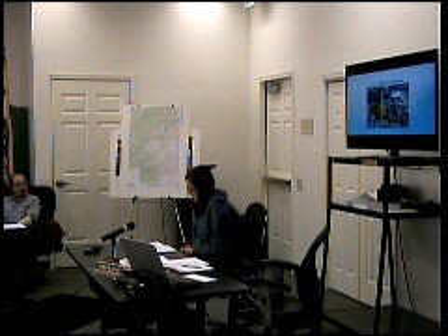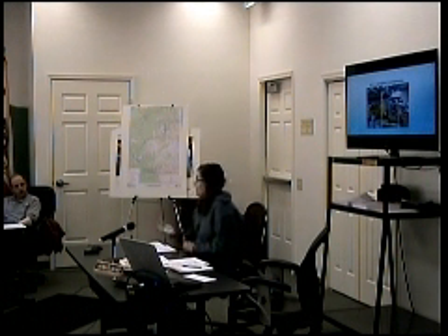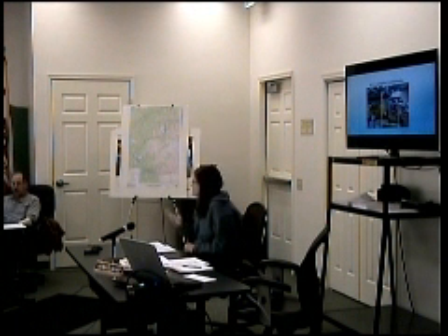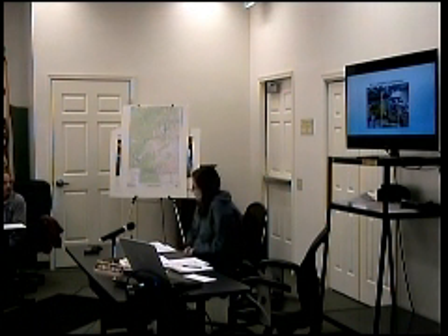We just dealt with a PLC communication issue. Back the week of 9/26, Wilson was wiring in the new switchgear to our current DC system, and they caused a short which took out our PLC that controls our automatic breaker function at the powerhouse and our generator control. So we had a series of outages over that week when we were able to initially bypass the PLC, which gave us manual control of the powerhouse, and then PowerSecure was on site within 2 days to further troubleshoot, replace a PLC, and replace a blown fuse.